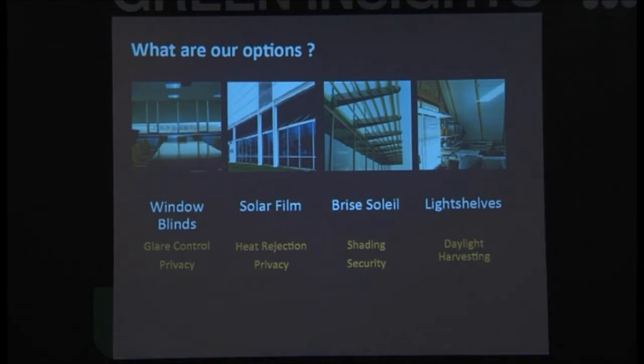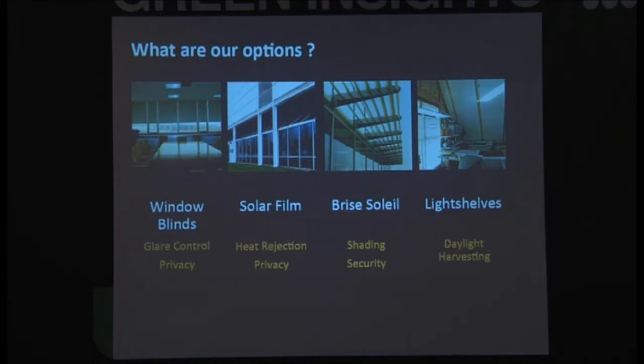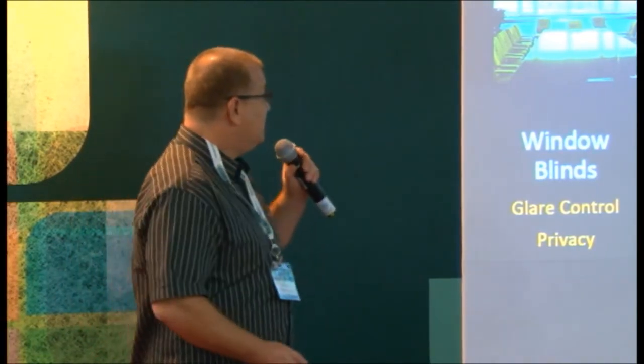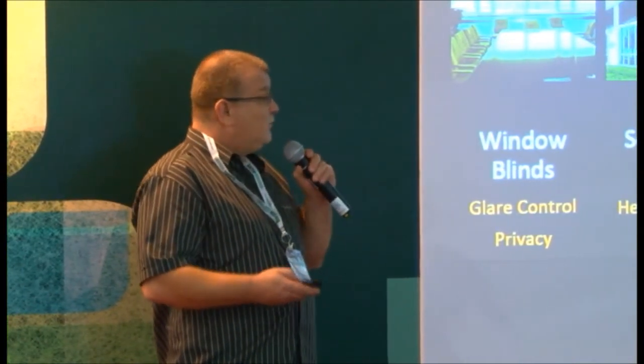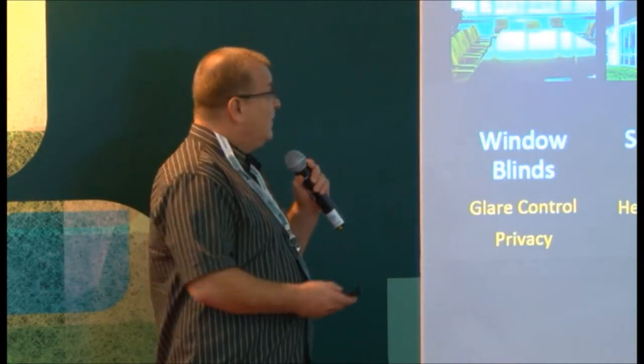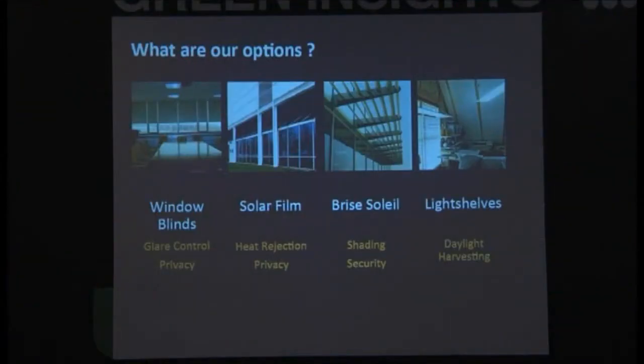So what are our solutions? Our solutions are window blinds, solar film, brise soleil and light shelves. Window blinds are great. They stop glare. But so do sunglasses and lots of other things. As I mentioned earlier, one of the problems with window blinds is the heat builds up behind them. Solar film, yes, it rejects heat. In some cases, to get the best heat rejection, we actually reduce the amount of light. One of the things it doesn't do is reduce a significant amount of glare. Brise soleil gives us exterior shading. Light shelves, because they work on direct reflection of light, and the sun moves up very quickly in Malaysia. Unless they're in the direct path of the sun, we don't really get much benefit from them.